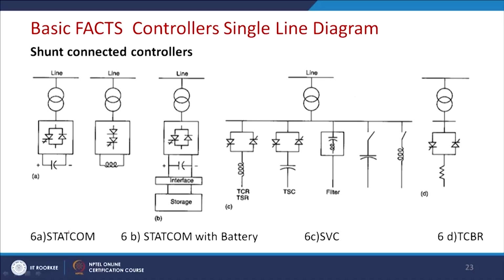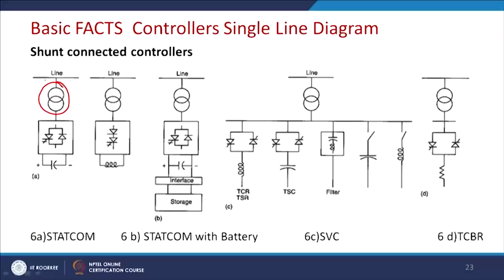This is the STATCOM. This stands for the step down transformer. Since operating devices cannot match the existing power line voltages, it is required to step it down. It is basically a static version of an over excited synchronous generator. A synchronous generator can provide this solution also, compensating the active power and also controlling the VAR of the line, but it can do that actively. But the advantage is that here only the switching loss has to be fed, and no prime mover is required. Thus the efficiency of the system is quite high in this case.